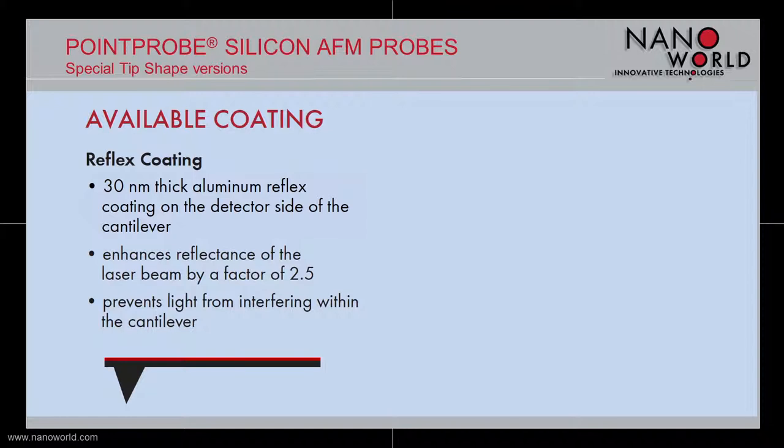For all Point Probe special tip shape probes, a 30 nm thick aluminum reflex coating on the detector side of the cantilever is available. This coating enhances the reflectance of the laser beam by a factor of 2.5 and prevents light from interfering within the cantilever.